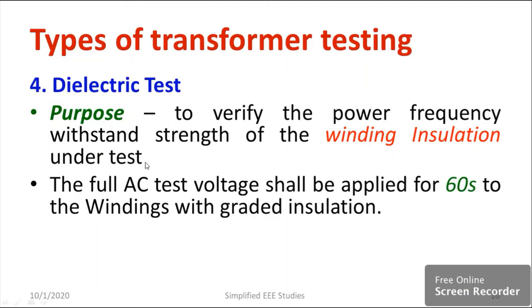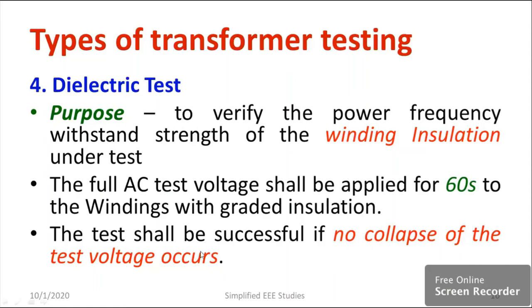I would like to discuss about the dielectric test. We conduct it to verify the power frequency withstand strength of the winding insulation. We need to produce a test AC voltage and apply it for one minute (60 seconds) to the transformer winding. Make sure no sudden drop occurs. The test is successful if there is no collapse in the test voltage; otherwise, the winding insulation needs to be replaced.